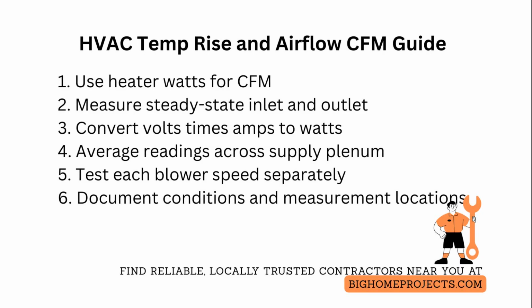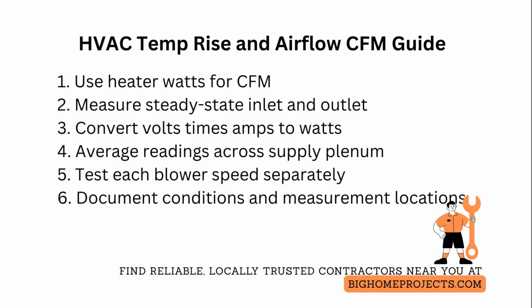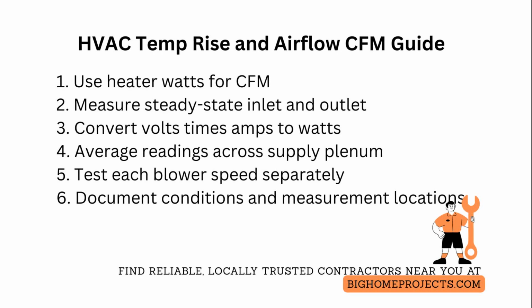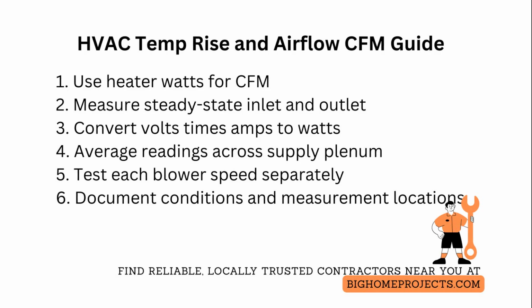Correct for multi-speed blowers by testing each speed separately and report CFM per speed. If the system uses variable frequency drives, lock to a steady frequency for the test. Always document ambient conditions and measurement locations so later field verification or code inspection can match your method.